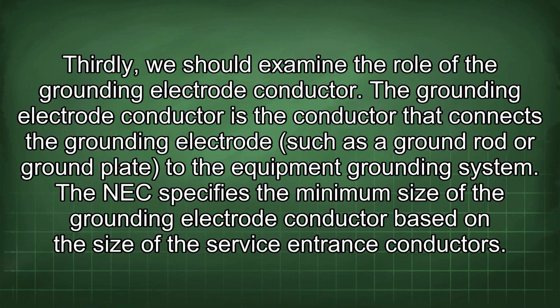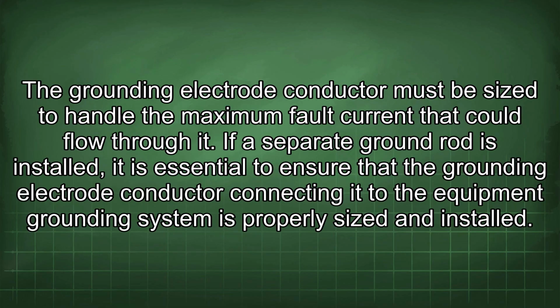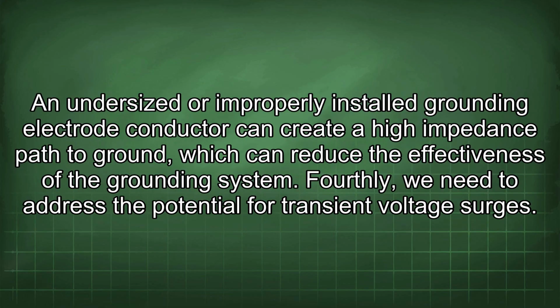Thirdly, we should examine the role of the grounding electrode conductor. The grounding electrode conductor is the conductor that connects the grounding electrode, such as a ground rod or ground plate, to the equipment grounding system. The NEC specifies the minimum size of the grounding electrode conductor based on the size of the service entrance conductors. The grounding electrode conductor must be sized to handle the maximum fault current that could flow through it. If a separate ground rod is installed, it is essential to ensure that the grounding electrode conductor connecting it to the equipment grounding system is properly sized and installed. An undersized or improperly installed grounding electrode conductor can create a high impedance path to ground, which can reduce the effectiveness of the grounding system.